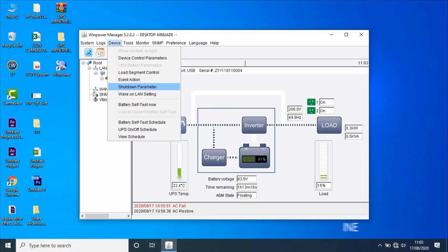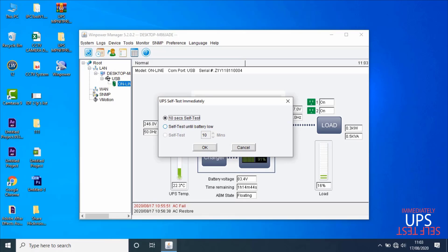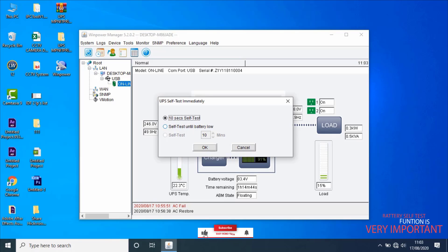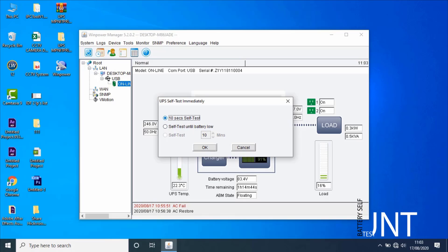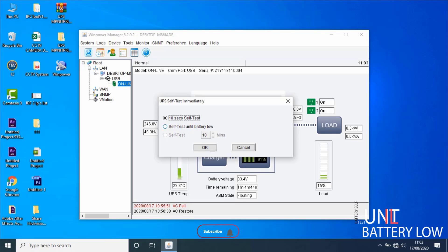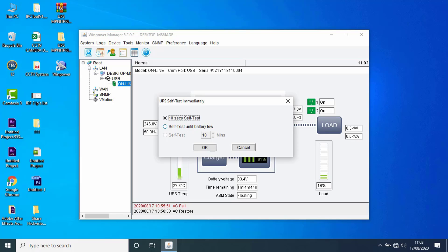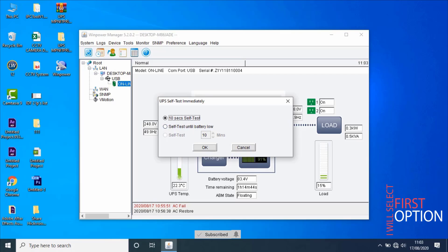Next, go to battery self-test. UPS batteries should be in good status to supply power for key devices when AC fails, so the battery self-test function is very important. Battery self-test includes self-test immediately and schedule test. There are three types: Type 1 — battery self-test for 10 seconds; Type 2 — battery self-test until battery low; Type 3 — battery self-test for N minutes, where N ranges from 1 to 99 with a default of 10 minutes. Let's test — I'll select the first option, battery self-test for 10 seconds, then click OK.